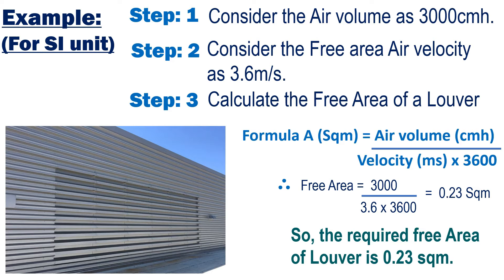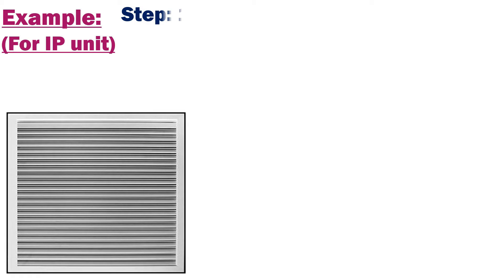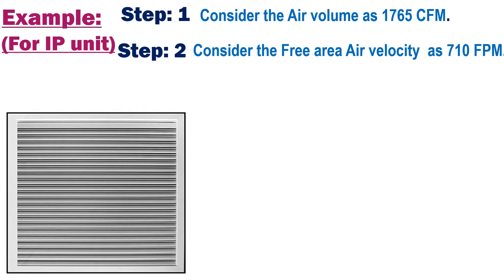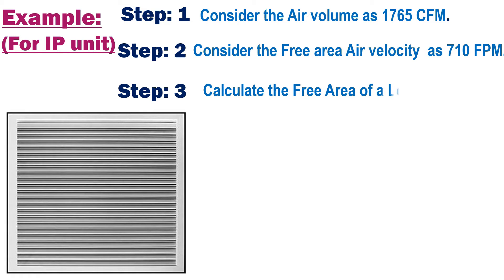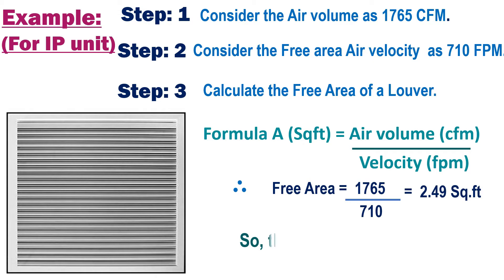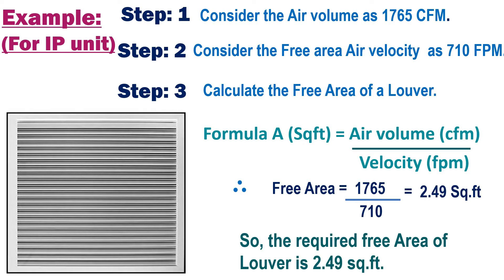Now go through an example for IP units. Step 1: consider the air volume as 1765 cubic feet per minute. Step 2: consider the free area air velocity as 710 feet per minute. Step 3: calculate the free area of the louver. The formula is: Free Area (ft²) = Air Volume (CFM) ÷ Velocity (FPM). Therefore, Free Area = 1765 ÷ 710 = 2.49 square feet.